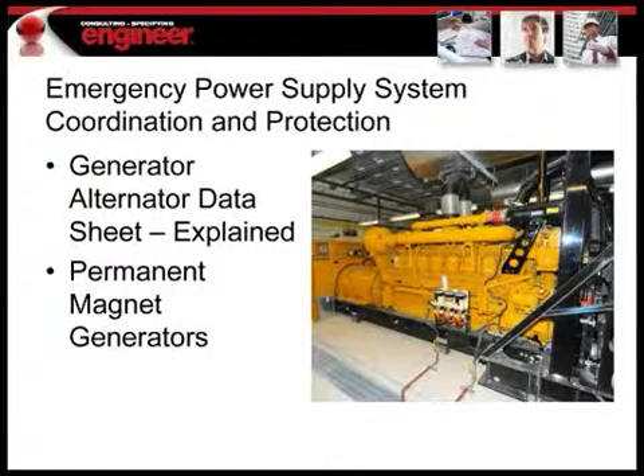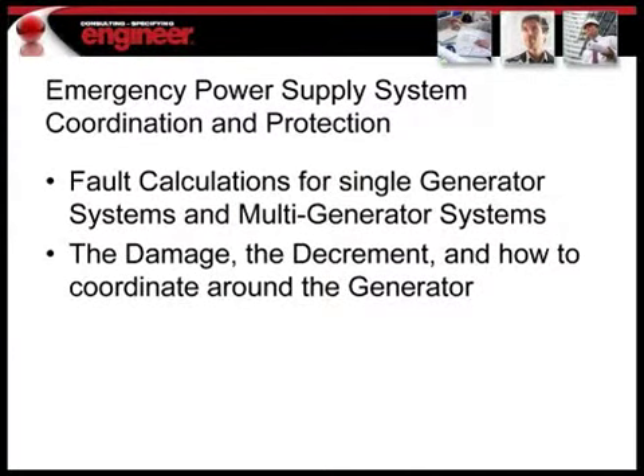We're going to talk a little bit about permanent magnet generators and what kind of effect they have on your protection and coordination. Then we're going to go into fault calculations for your generators, how to take that alternator data and calculate the fault for your generator, and also look at how that impacts a multi-generator system. And finally, we're going to go into the actual coordination of the protection with the generator. That includes the damage curve, the decrement curve, and how to really lay out your breakers so that they allow the system to function properly.